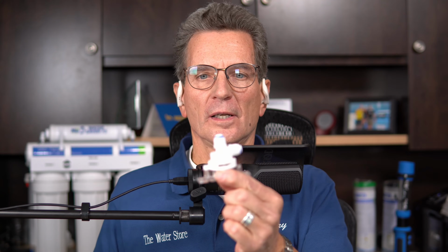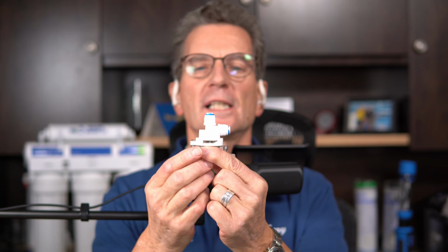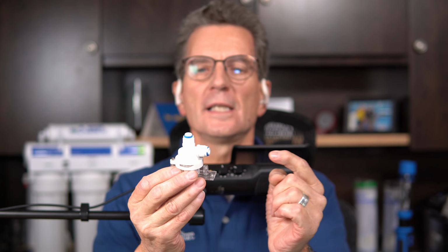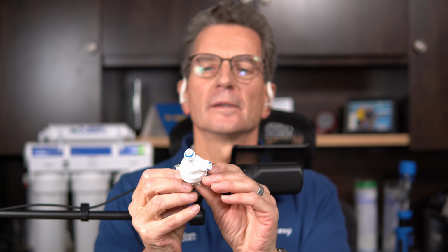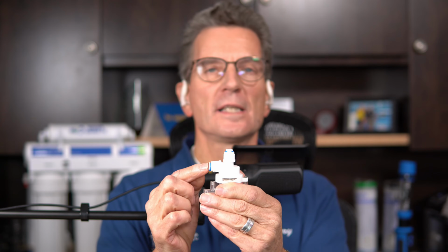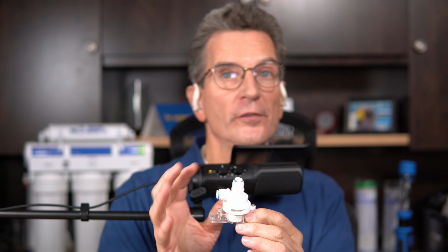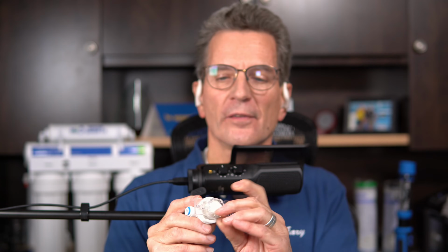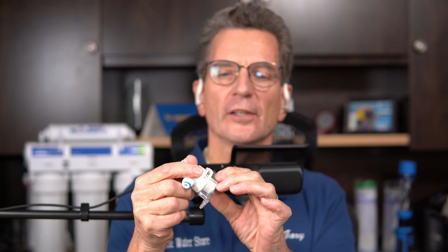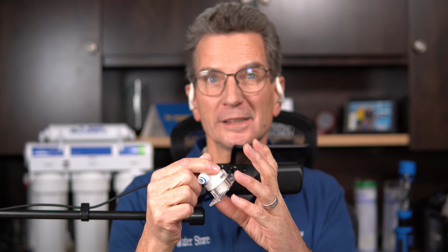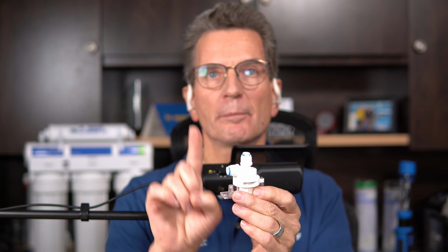And basically how it works is, I'll hold it up here, maybe you can see it a little bit better. Water flows into the system here and then flows back out through here. If there's a spill or any water in here, even just a couple of drops, there's a pill at the bottom here. I don't know if you can see that or not. The pill expands relatively quickly, you'd be surprised. It has a plunger inside here that pushes up and shuts off all the water. So if you get a leak in that area, then it shuts it off.